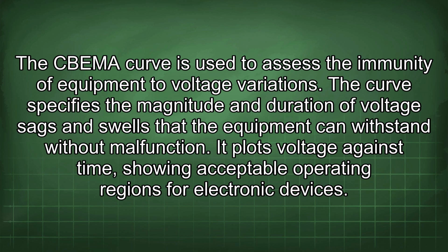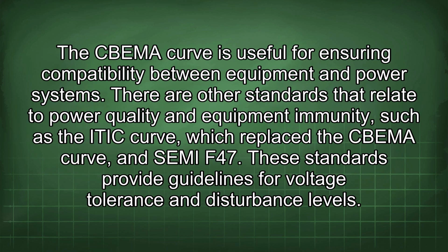The CBEMA curve is used to assess the immunity of equipment to voltage variations. The curve specifies the magnitude and duration of voltage sags and swells that the equipment can withstand without malfunction. It plots voltage against time, showing acceptable operating regions for electronic devices. The CBEMA curve is useful for ensuring compatibility between equipment and power systems.